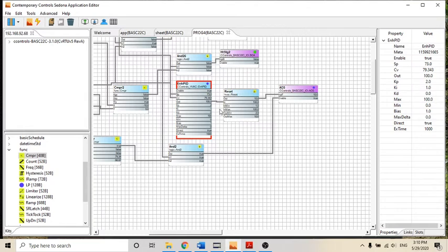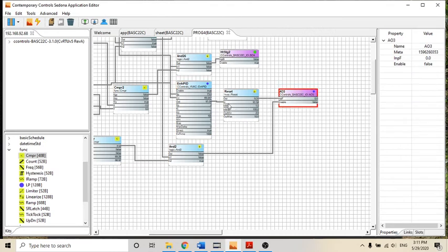I'm going to go ahead and stick my thermistor into the cold water, so it's going to start getting colder and colder, and that way we'll be able to observe how the temperature in the zone is going to go down, how we're no longer going to be in cooling, and the minute we are no longer in cooling, it will go ahead and shut off. So there, we are not in cooling, it shut off, and as you can see, the reset value was already getting down. So it's still not perfect because I am still going down in temperature too fast, faster than my reset block can actually send a signal correctly.